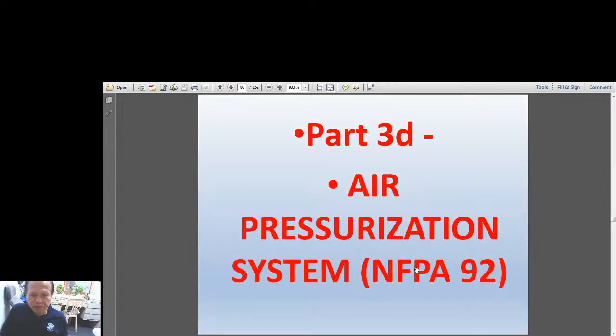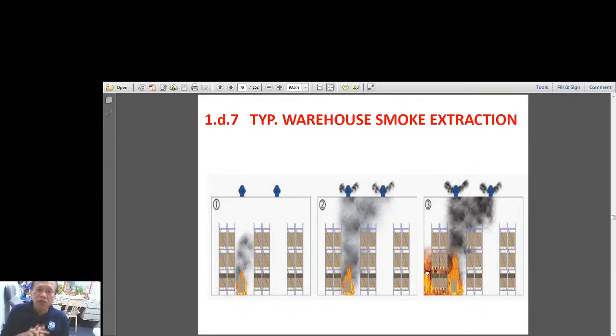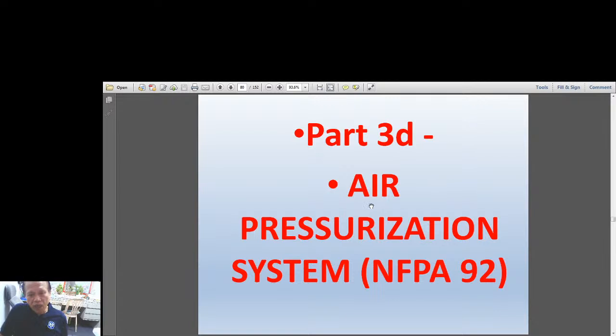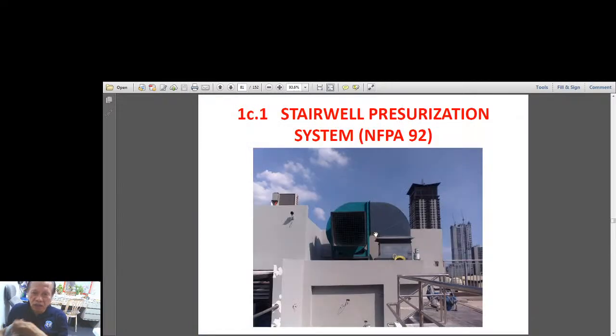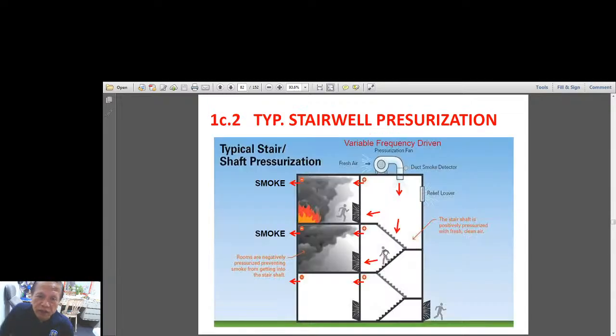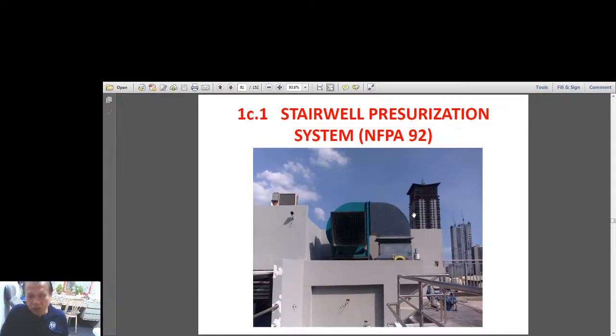Okay. So now we're through with toxic gas detection and extraction, as well as smoke extraction. Now we proceed with the next topic, air pressurization. The fire exits must be assured to be safe for people to run through, in order that the people running for their safety to the fire exits will have a greater chance of not being suffocated. So here is a picture of a stairwell fan. A pressurization fan. It's not an exhaust fan. It is a fan that gets fresh air from outside of the building and puts it inside the stairwell, at the top of the stairwell.